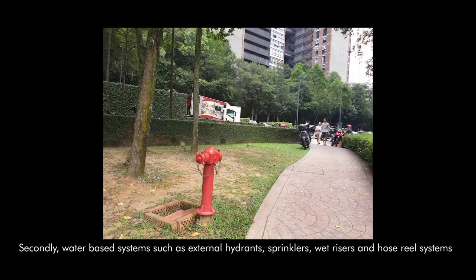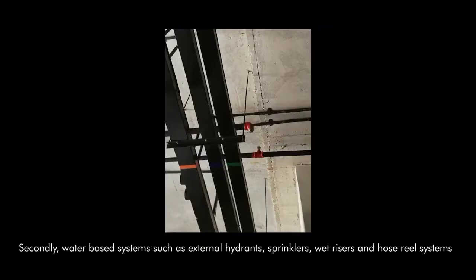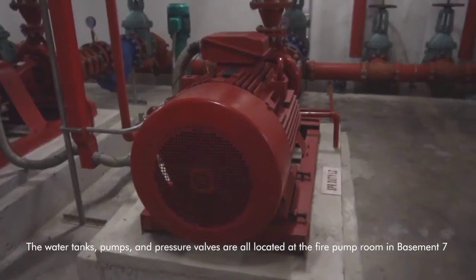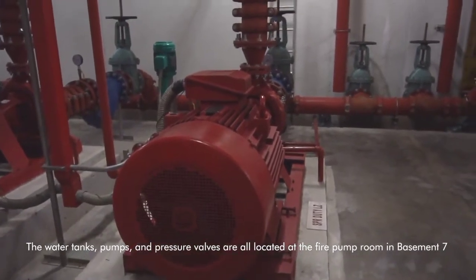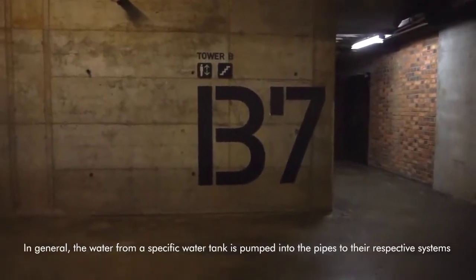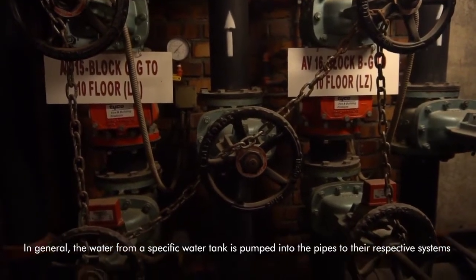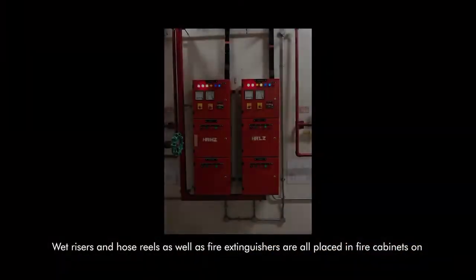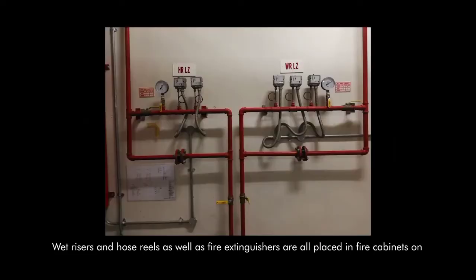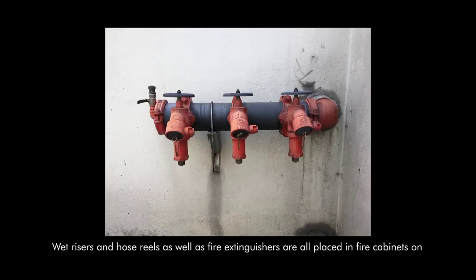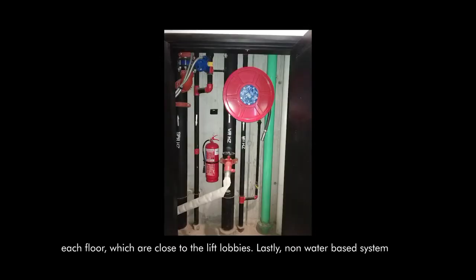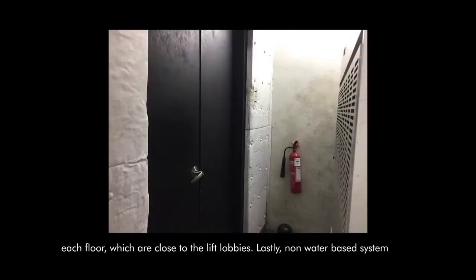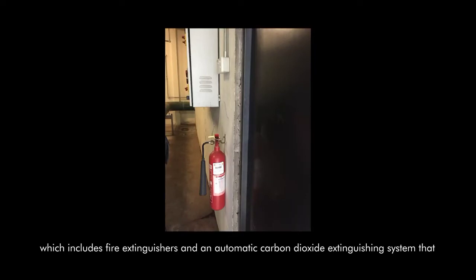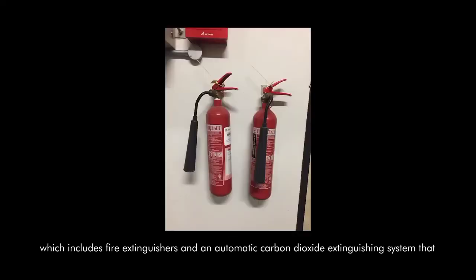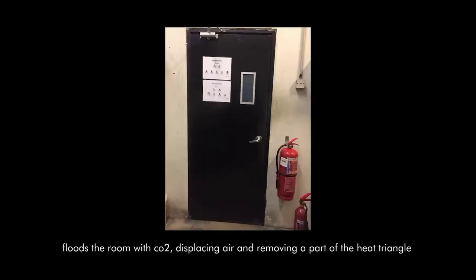Secondly, water-based systems such as external hydrants, sprinklers, wet risers, and hose reel systems. The water tank, pumps, and pressure valves are all located at the fire pump room in basement 7. In general, the water from a specific water tank is pumped into the pipes to their respective systems. Wet risers and hose reels as well as fire extinguishers are all placed in fire cabinets on each floor, which are close to the lift lobbies. Lastly, non-water-based systems, which include fire extinguishers and an automatic carbon dioxide extinguishing system that floods the room with CO2, displacing air and removing a part of the heat triangle.